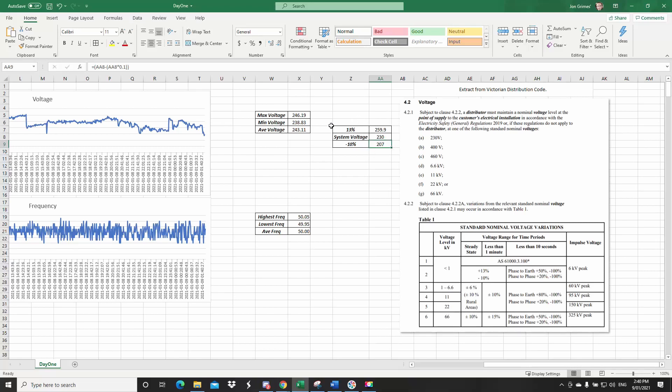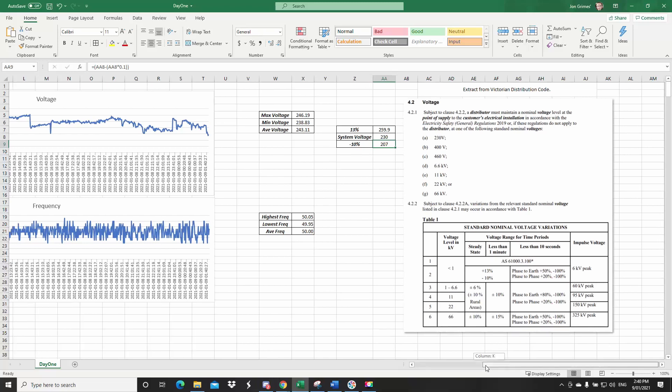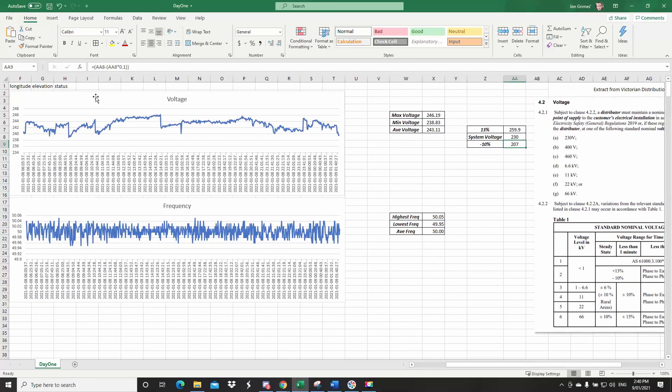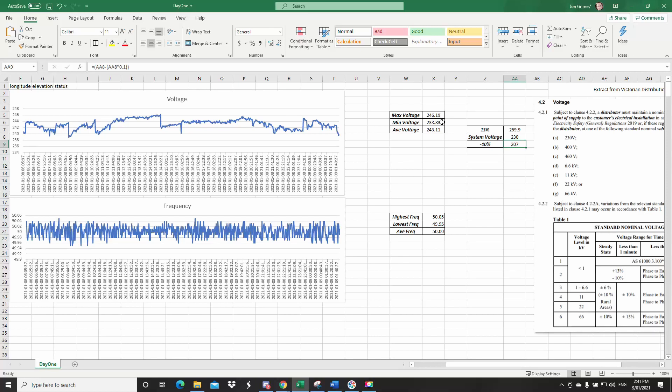So if I've taken my data from the graph, or from the actual column of data, I've taken my maximum voltage for that period of time. So this is roughly a 24 hour day. So this is 246 volts, or 246.19 volts is the highest I've got for that period of time. The minimum, 238.83. So the average voltage was 243. So that's well within the tolerance.